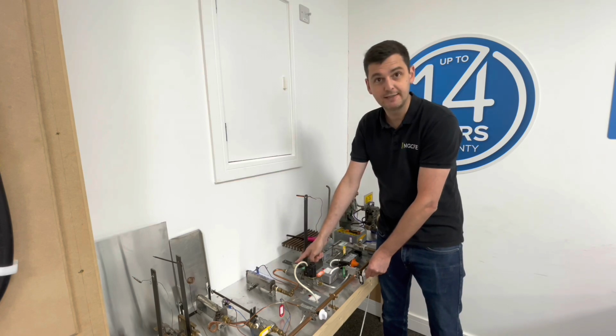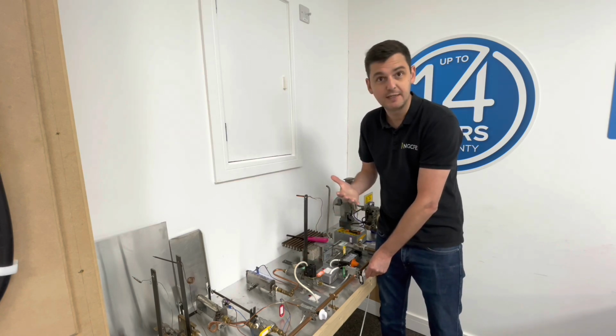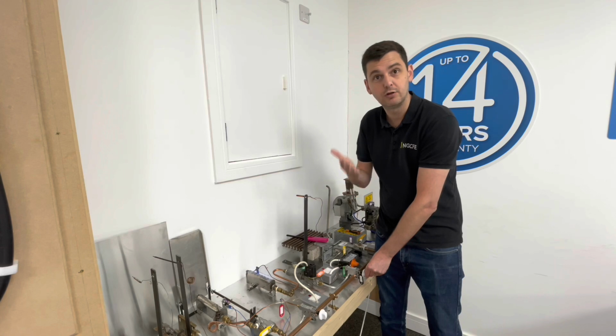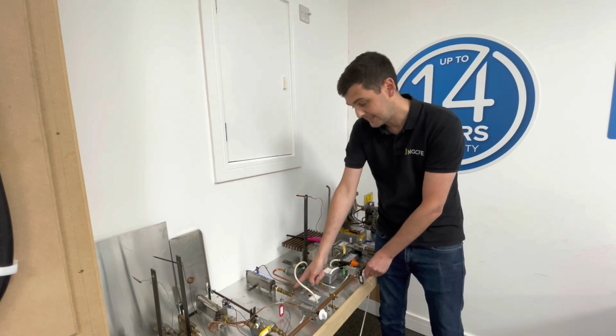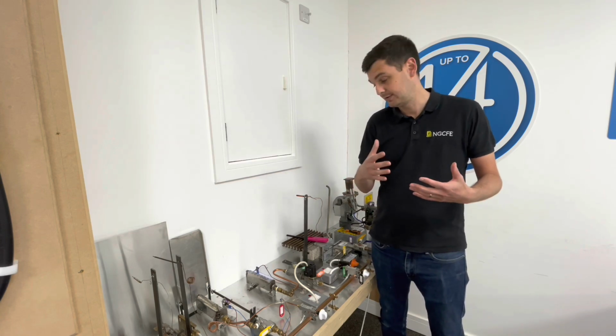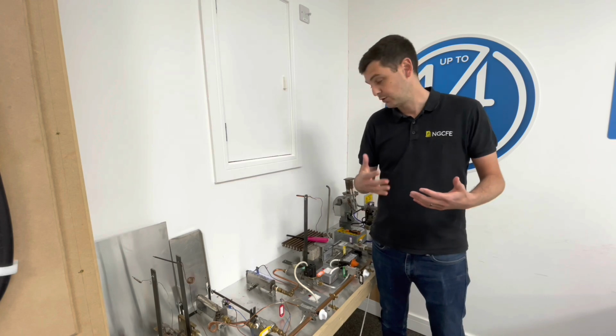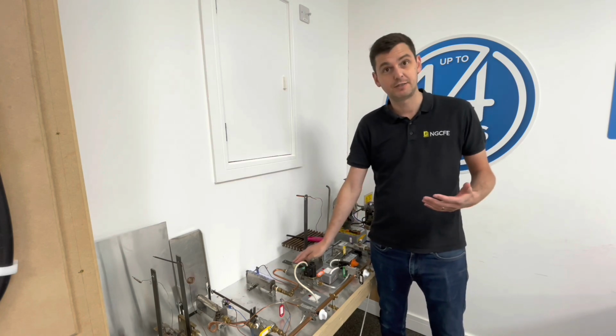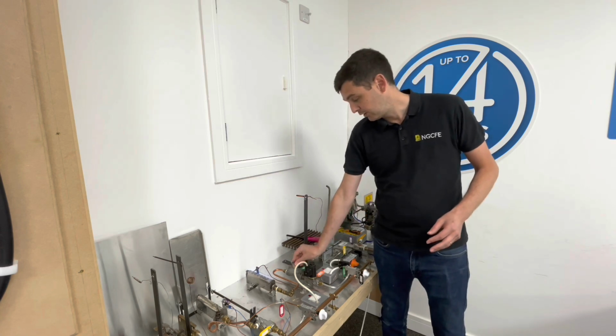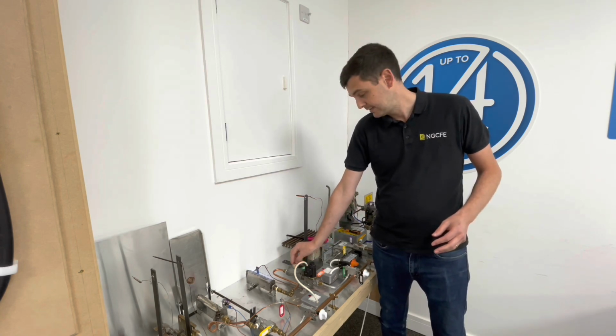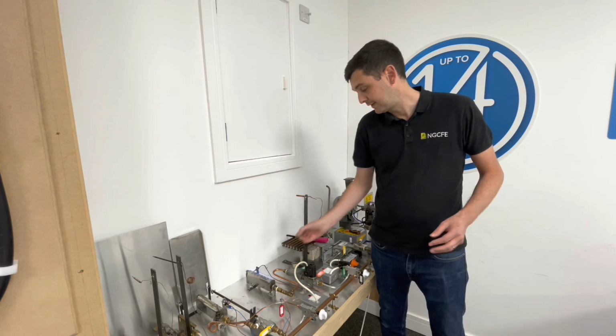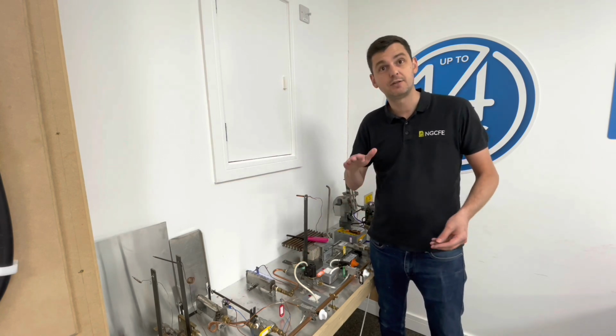The low pressure regulator, the way to think of it is you treat it exactly the same way as you would on a gas meter. We've got a test point that we can connect the manometer to, and all we want to make sure is that we've got the relevant outlet pressure, or the relevant pressure that we would expect to get from this regulator. If we haven't, again, we've got the adjustment point on top of the regulator where we can use a flathead screwdriver and we can change the outlet pressure.